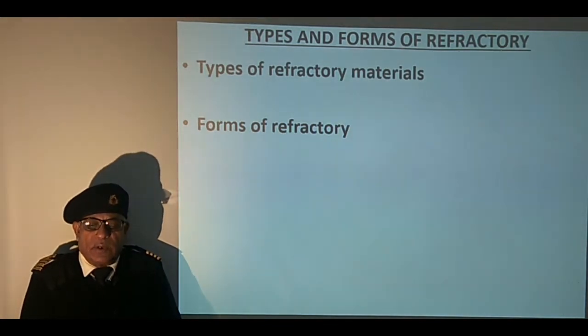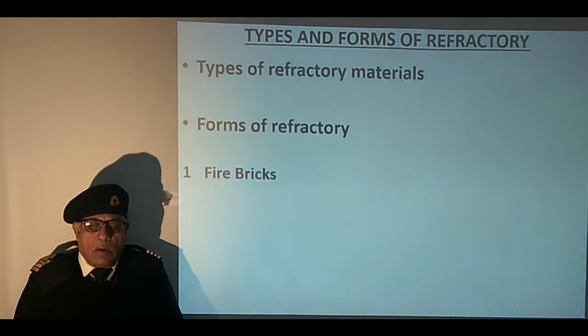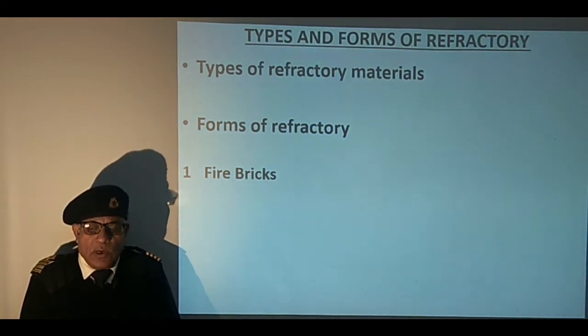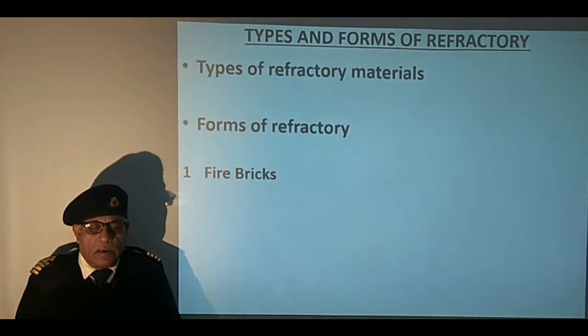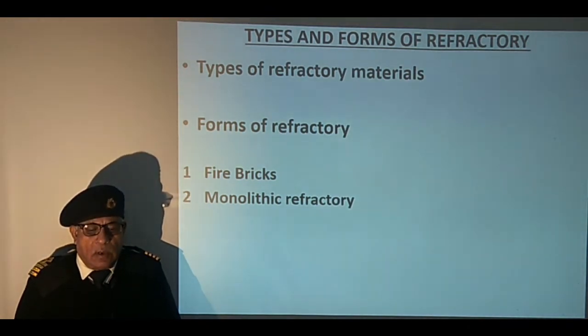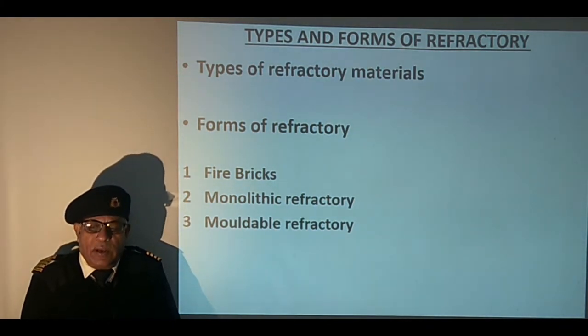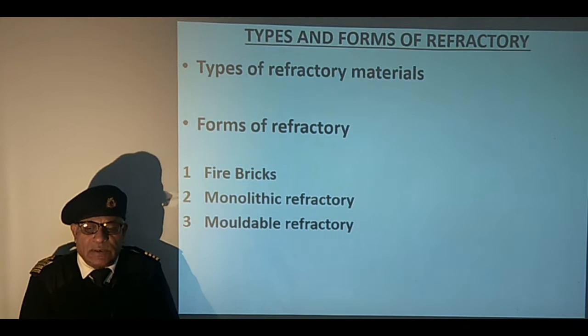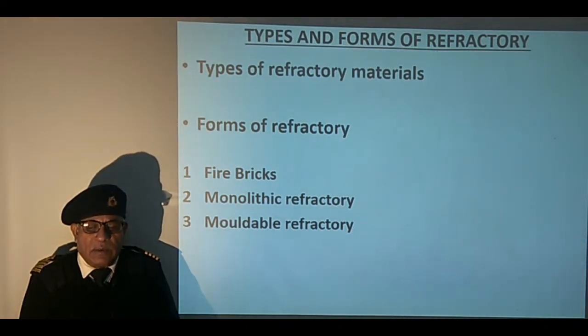Refractory may be available in one of the following forms. Fired bricks are made from natural clay containing alumina, silica and quartz; they are shaped into bricks and fired in a kiln. Monolithic refractory is supplied in the unfired state, installed in the boiler and fired in situ when the boiler is commissioned. Moldable refractory is used where direct exposure to radiant heat takes place; it must be pounded into place during installation and is made from natural clay added with calcified fire clay which has been crushed and graded.